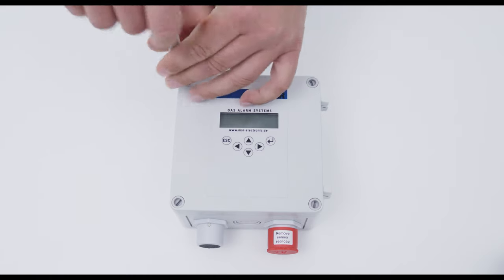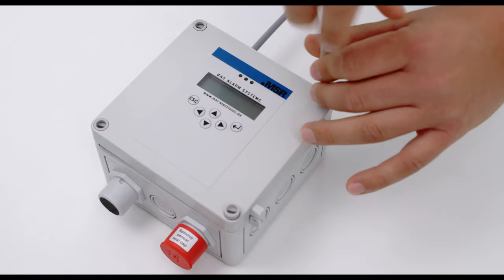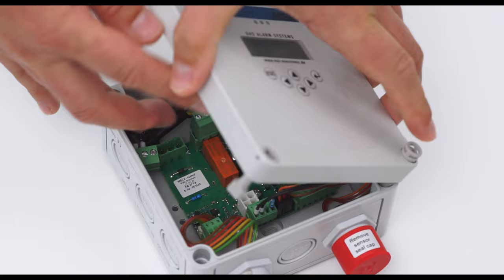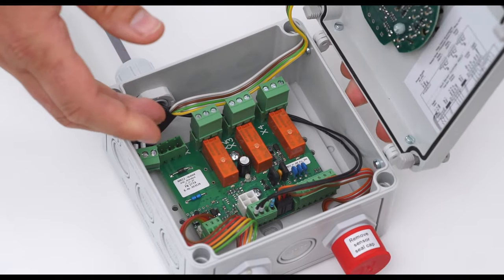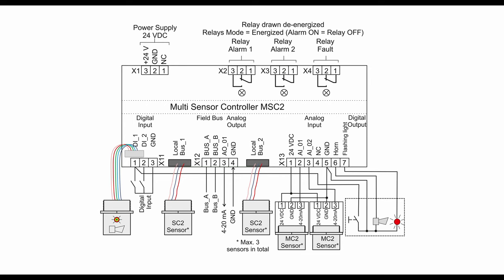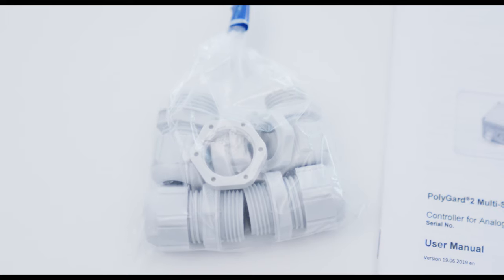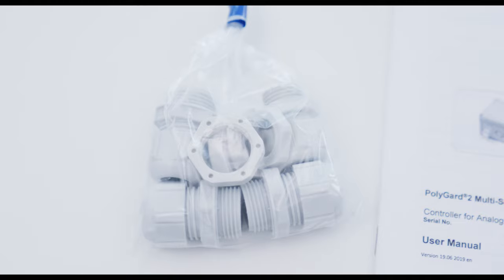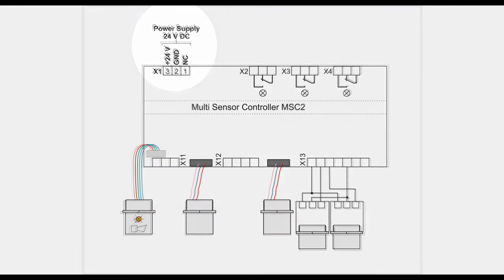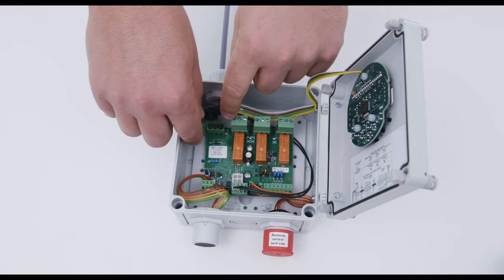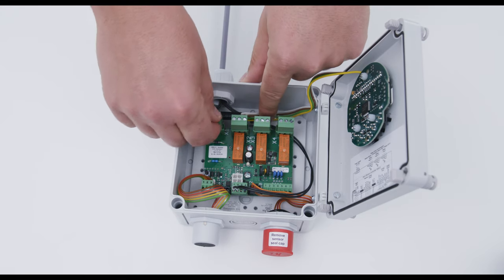First remove the screws of the cover. A detailed connection diagram is provided in the cover. To connect the power supply, the cable gland in the accessory pack must be used to protect the housing. Connect voltage at X1, 24V DC at the X1.3 and ground at the X1.2.